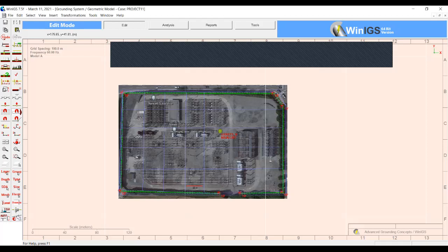Now that soil resistivity data you have to put into the software. Now the software knows that this is your grounding grid, that much conductor you are having, that is the fence you are having, that's the counterpoise, everything you have, and based on that your analysis will be done. But we are not going to do the analysis today. We'll use the soil resistivity, considering that the soil resistivity measurement was done surrounding these substations, whatever substations you are working on.